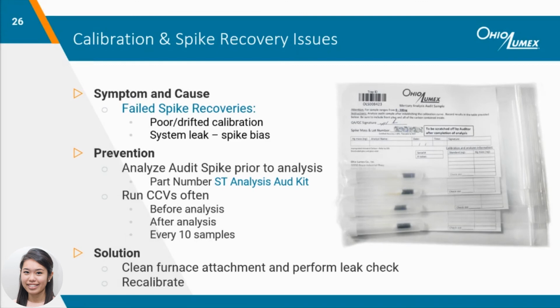Lastly, failed spike recoveries can result from a calibration that has drifted or a leak in the system that leads to spike bias. The most common reason for failing spikes is due to spike bias. Spike bias is the difference between oxidized mercury or liquid mercury used to calibrate and elemental mercury or vapor phase mercury used to spike sorbent traps. This often flies under the radar because CCVs using liquid standards can still pass within the allotted 10%. The best laboratory practice is to analyze an audit spike or burn an unused spike trap prior to running any samples to ensure the sorbent trap results are accurate.